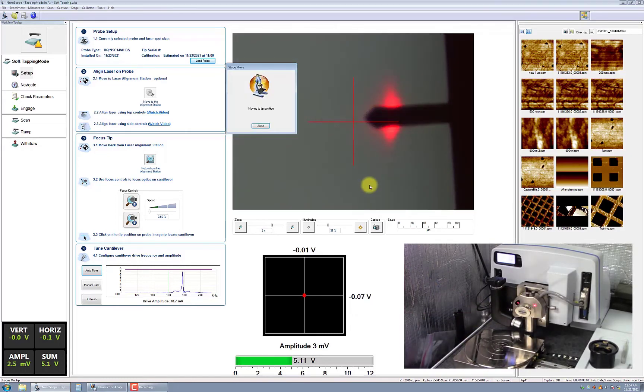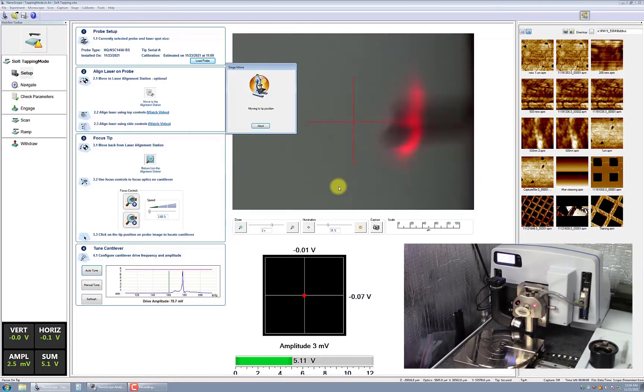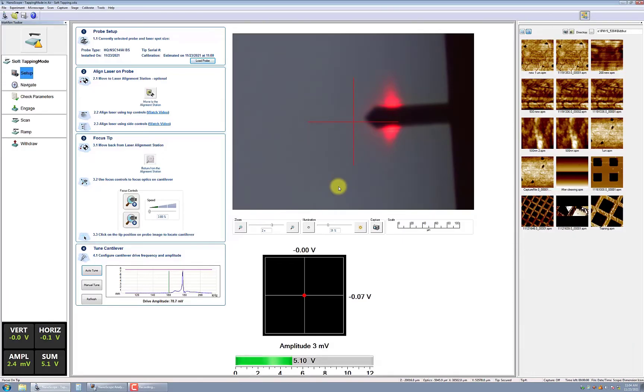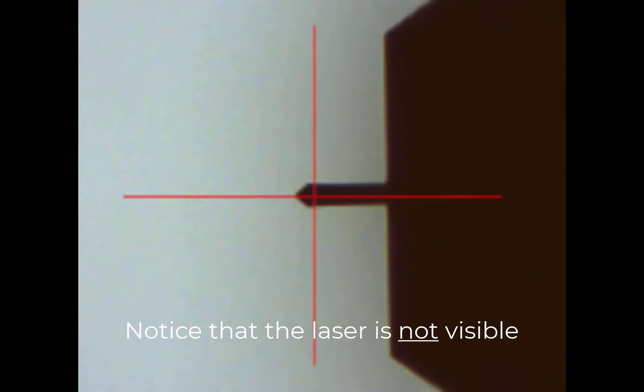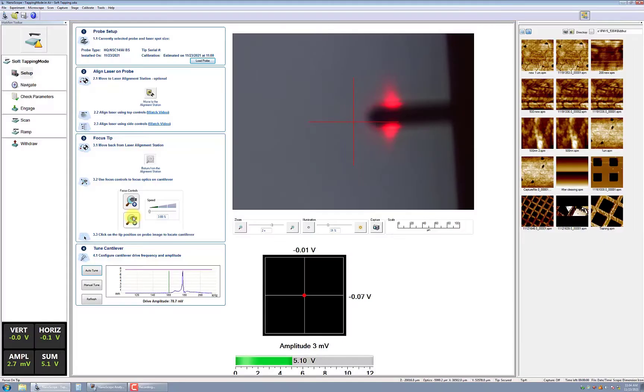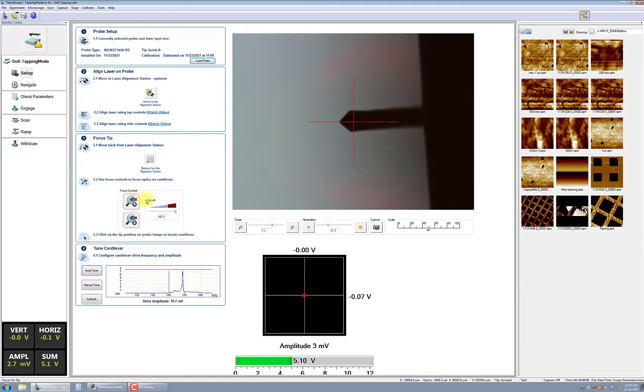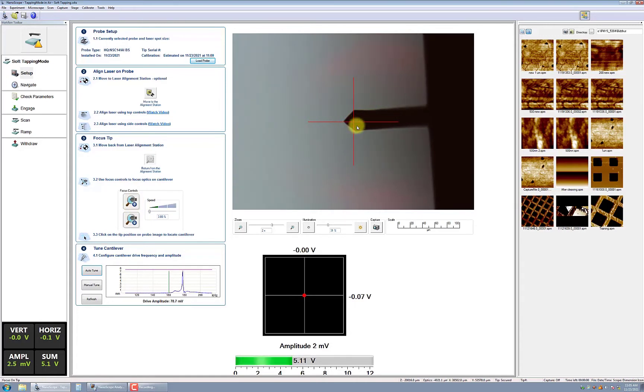Next, refocus on the cantilever, not the reflection. The image should look like this. If the image looks like this, increase the focus speed and move the scan head up and slow the speed to achieve a fine focus. Now, move the cross to the approximate position of the tip, which is at the vertices of the three points.